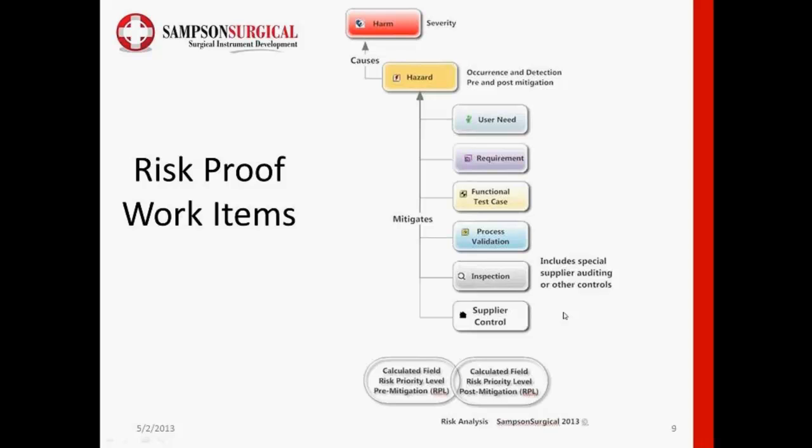So the second piece of this is really the risk. We're finally getting around to the risk proof. Typically, in a lot of different industries, you'd have a DFMEA risk analysis methodology that would start with a cause and effect kind of setup, but in medical device, of course, we're more interested in patient harm or user harm. And so the methodology that we employed here is to start with the harms and then have hazards. And of course, it's a one-to-many relationship again. Multiple hazards can cause any particular harm. And then these same tests that we use in the V&V tests are mitigations to those hazards.